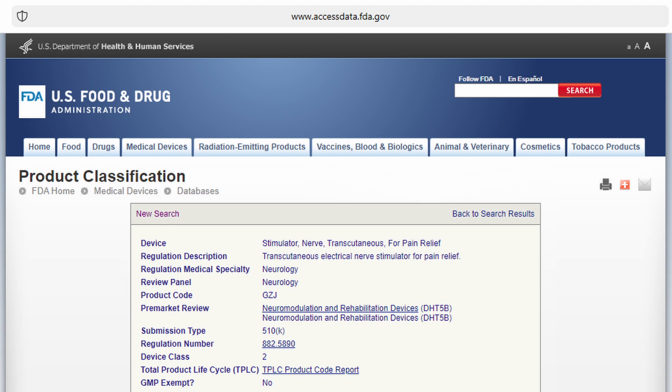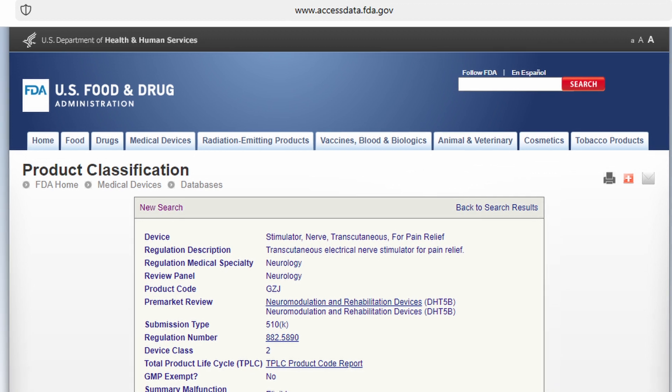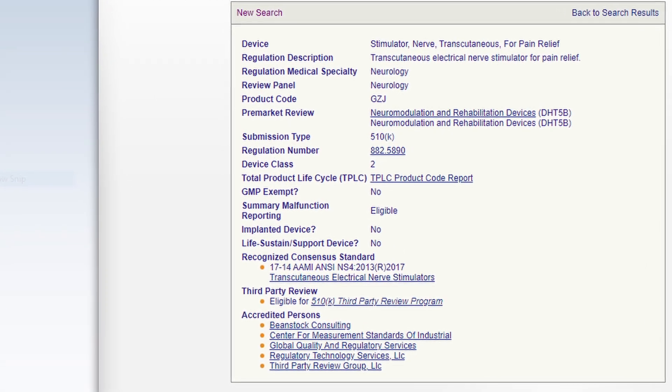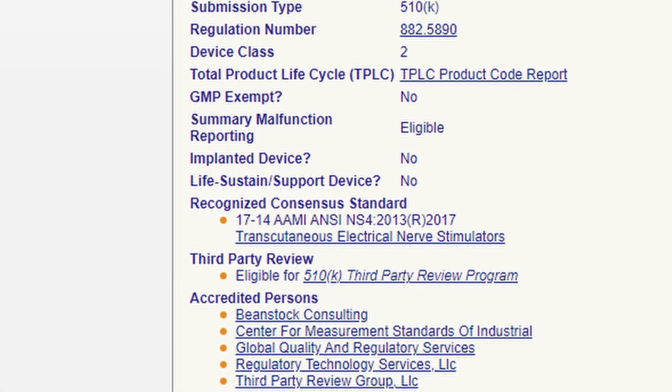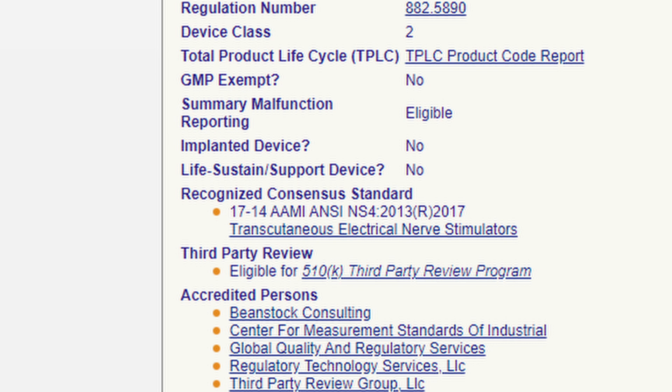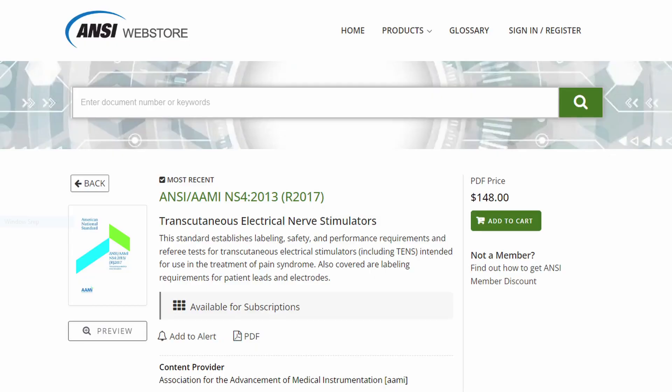For example, in recent years, TENS units — or transcutaneous electrical nerve stimulators — have been cleared by FDA for everything from congestion to pain relief. Here's an example from the FDA website of a product code for a TENS unit for pain relief. When you look at this page, beyond the information on the product code, device classification, and submission type, you'll notice a recognized consensus standard listed: 17-14 from AAMI ANSI NS4 2013 with revision in 2017. That standard covers requirements for portable battery-powered transcutaneous electrical nerve stimulators used in the treatment of pain syndromes.